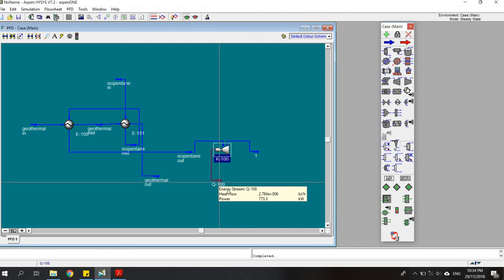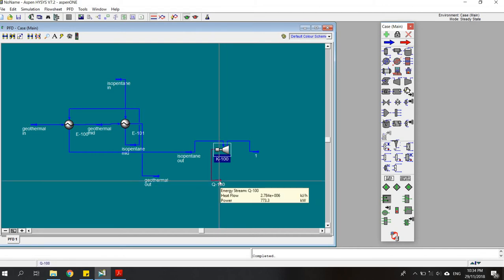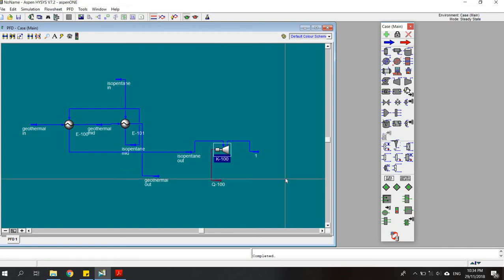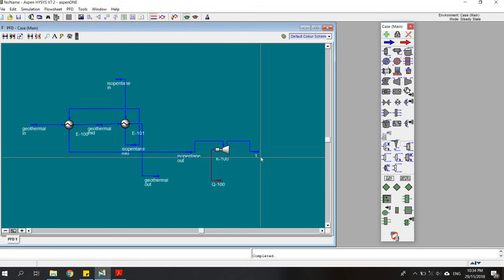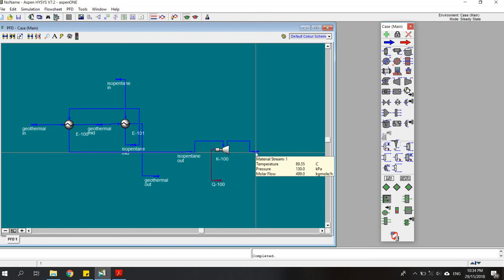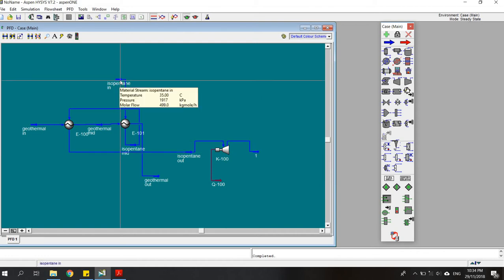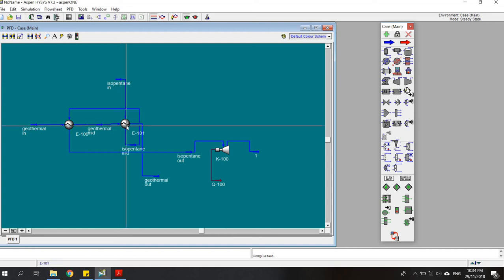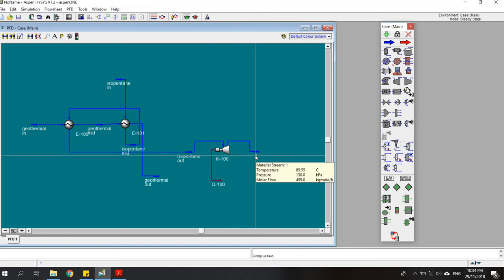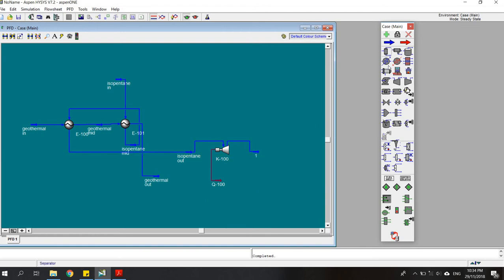After that, we can check how much energy we can get, which is 773.3 kilowatts. The outlet of the turbine would be around 89 degrees Celsius, but we want 35 degrees Celsius, the temperature entering the heater. So we have to cool down this temperature, and I'm going to use an air cooler.